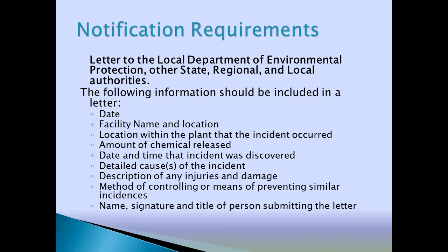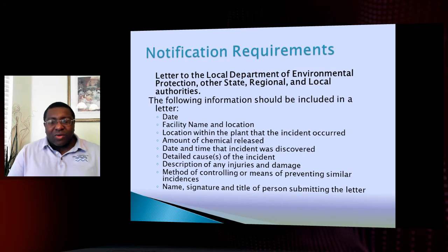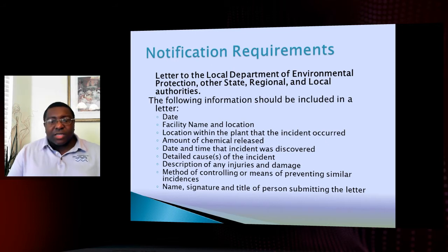The notification must have a date, your facility name and location — not only your physical address but GPS coordinates of your process so they know exactly where the bulk tank is. Include the amount of chemical released, the date and time of the release, and when you discovered it, because sometimes those are different. For example, if you have a telemetry system monitoring tank level and an alarm is triggered, an operator may not discover it until they return to their station.